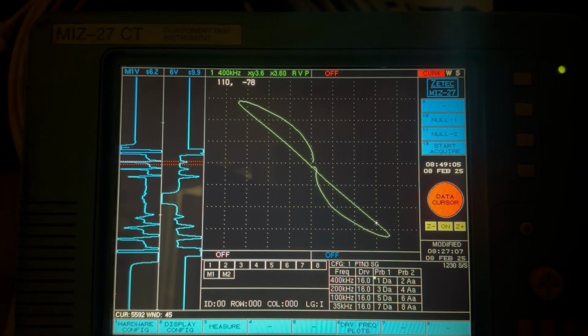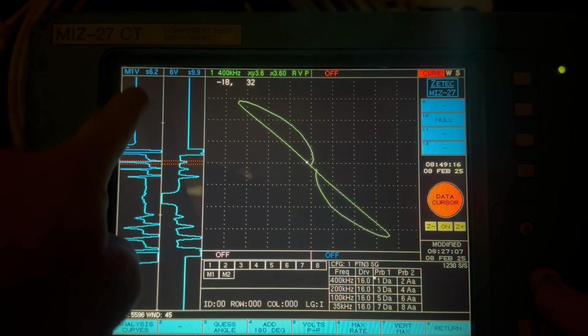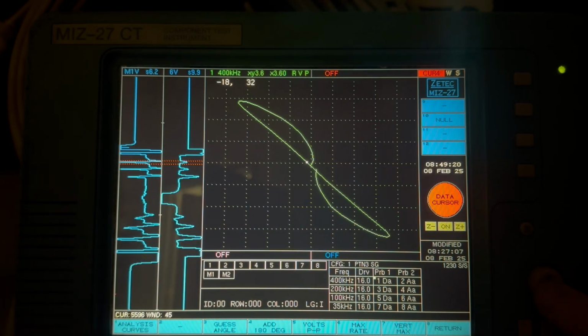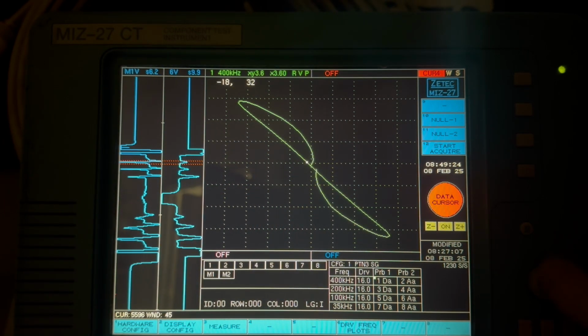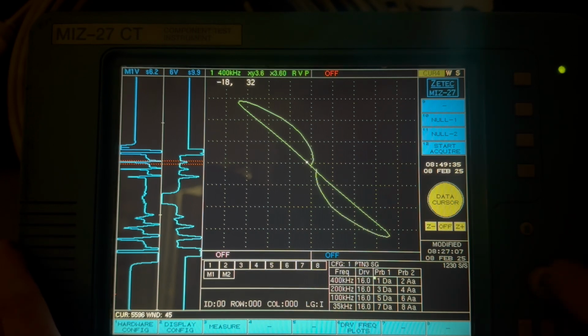Alrighty then. So to start off, this particular calibration has already been set up perfectly. If you look at my left strip chart, I've got a mix 1 vertical. Right strip chart, I've got channel 6 vertical. And in my Lissajous, we're looking at channel 1. So that has the 100% hole signal rotated to 40 degrees, which is typical for most bobbin coil exams.